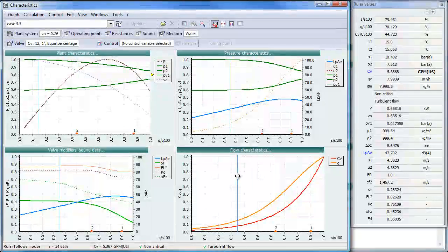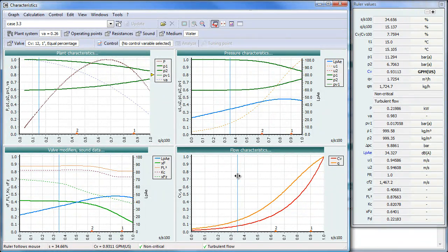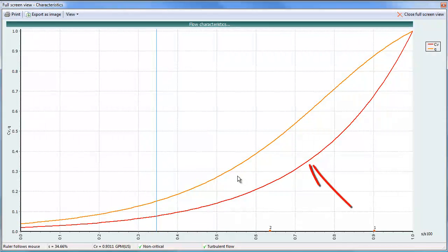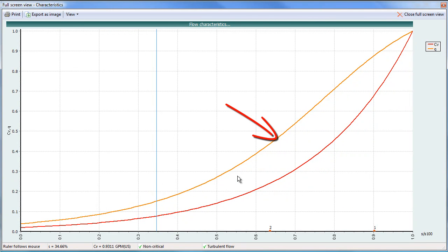On the bottom right is the flow characteristic curve. The red line is the inherent or the basic characteristic — we selected an equal percentage. The brown, or brown-orange, line is actually the installed characteristic, which is directly in function of flow.